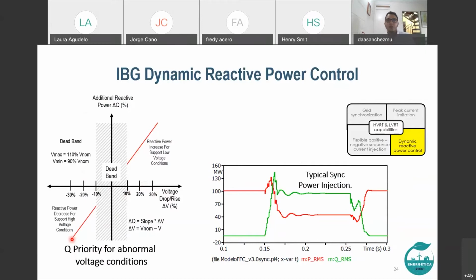On the right side, we can see the typical power injection behavior of a synchronous machine. Because the grid elements are mainly inductive, when a short circuit occurs, the reactive power increases, here the green, and the active power decreases. So when we implement this IBG dynamic reactive power control on our IBG controlled current source model, we try to replicate this kind of behavior.